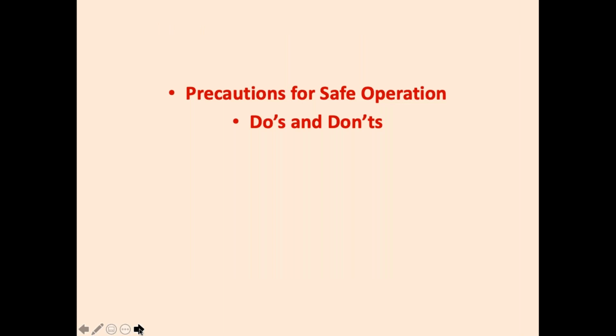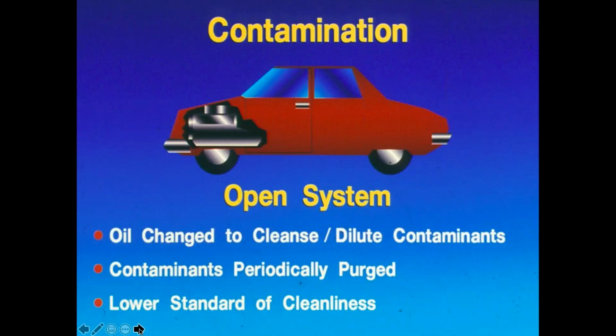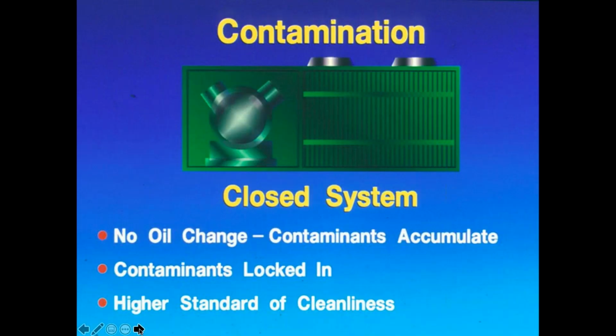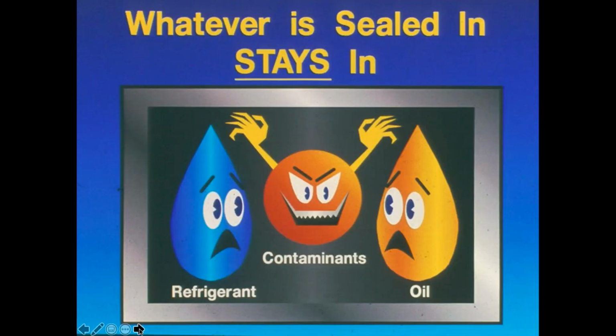Precautions for safe operation, dos and don'ts. Don't allow any contamination in the system. In an open system, you can always change the oil and remove the contaminants, like we do in our car. When you purchase a brand new car, they say change the oil after so many hours. It cannot be done in a closed system. Whatever remains in the system till the breakdown takes place, it remains in the system. So ensure that there are no contaminants inside the system because it is a closed system.